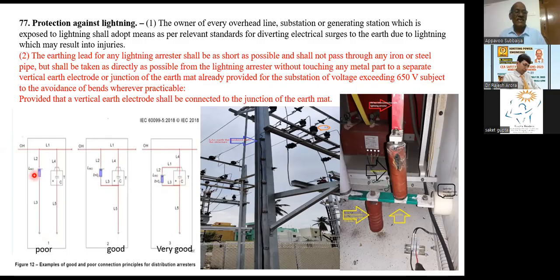It will damage the lightning arrestor instead of protecting the equipment, say the transformer. So the LA will become the weak link. It will be fused. Its purpose is to protect the transformer. A transformer, for example an 11 kV transformer, will have a basic insulation level of 75 kV. So your lightning arrestor should operate first because of the BIL of the transformer. This is the insulator, but they just connect it. Here it is a manufacturer's panel. So these are the things where people misconstrue and misapply.